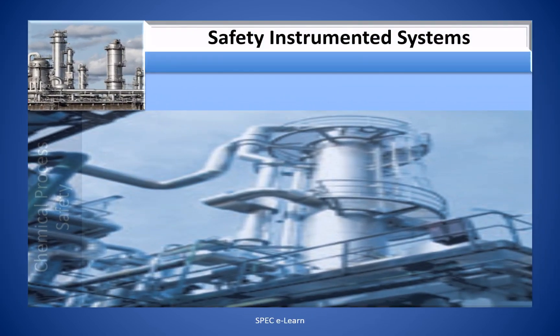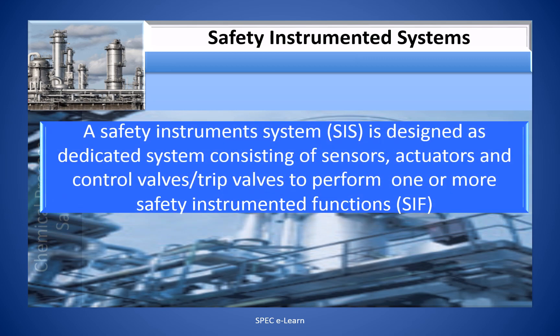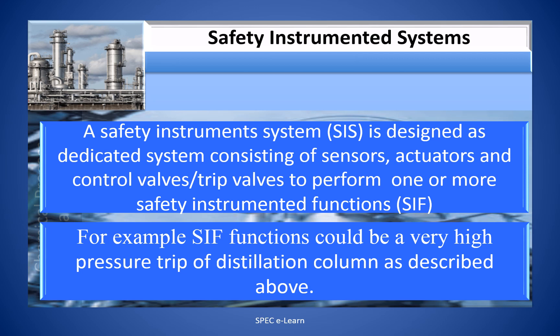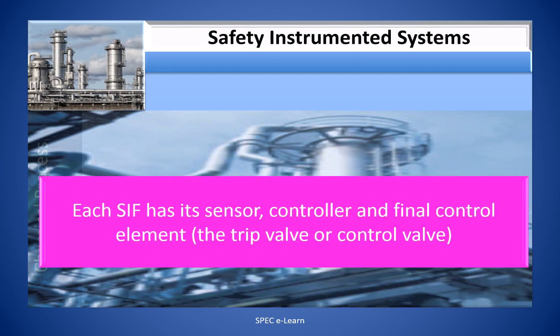A Safety Instrumented System is a dedicated system consisting of sensors, actuators, and control valves or TRIP valves to perform one or more Safety Instrumented Functions. For example, a SIF could be a very high pressure TRIP-off on a distillation column as described above. Each SIF has its own sensor, controller, and final control element, including a TRIP valve or a control valve.